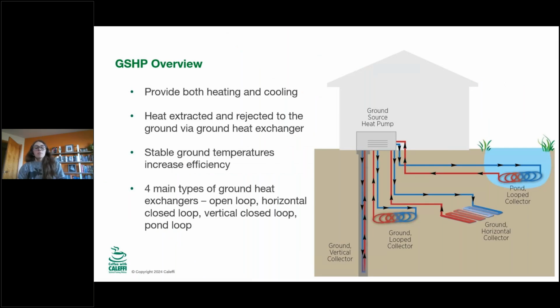So just a quick overview. I'm sure most of you are pretty familiar with what ground source heat pumps are, GSHP as they'll be referred to going forward. If anyone has questions, please drop them in the chat. This technology provides both heating and cooling within one unit, that heat pump. Heat is extracted and rejected to the ground via a ground heat exchanger. On the right are the different types of ground heat exchangers, which I'll get into in a second. One of the key staples of ground source heat pump technology is that they take advantage of stable ground temperatures to increase efficiency, especially compared to air source heat pumps.